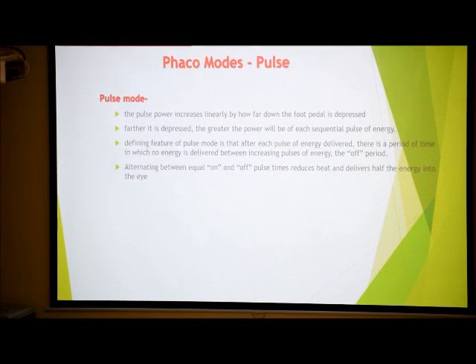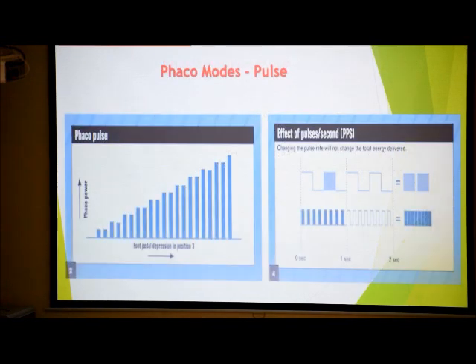Pulse mode: as we increase the excursion of the foot pedal, the amount of energy dissipated into the eye is more. The more the foot pedal is depressed, the more power is delivered into the eye. In the extreme grade of excursion, the power is almost 100%. But pulse mode is defined by an off time and an on time. On time is when the phaco power is delivered into the eye. Off time is a gap.